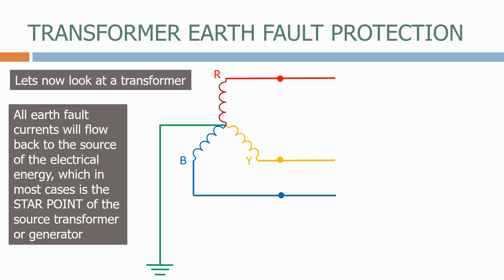All earth fault currents will flow back to the source of the electrical energy, which in most cases is the star point of the source transformer or generator.